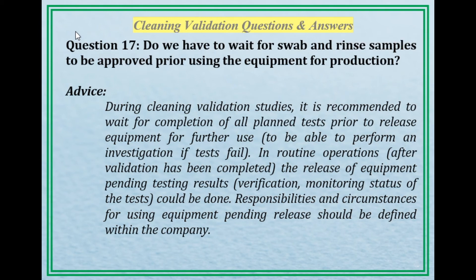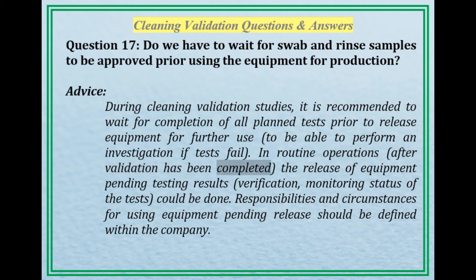Question 17: Do we have to wait for swab and rinse samples to be approved prior to using the equipment for production? Advice: During cleaning validation studies, it is recommended to wait for completion of all planned tests prior to releasing equipment for further use, to be able to perform an investigation if tests fail. In routine operations after validation has been completed, the release of equipment pending testing results could be done. Responsibilities and circumstances for using equipment pending release should be defined within the company.